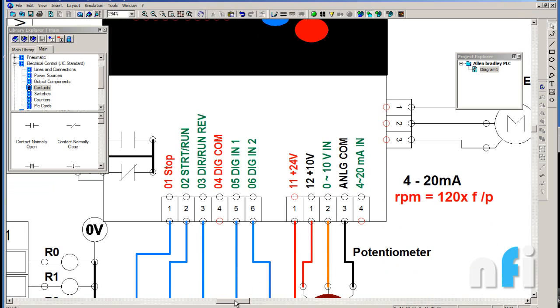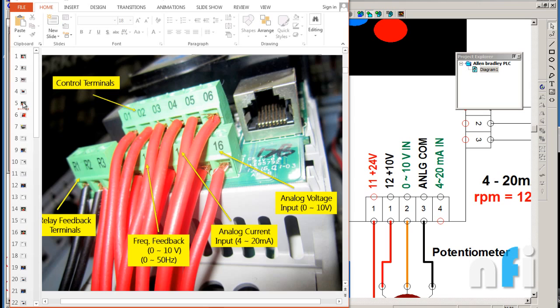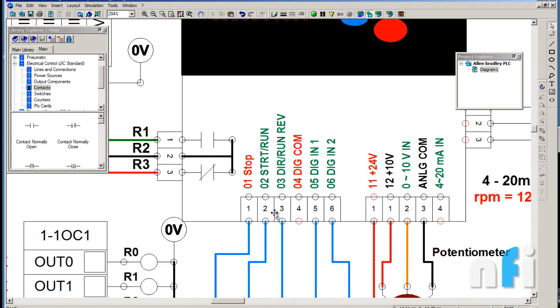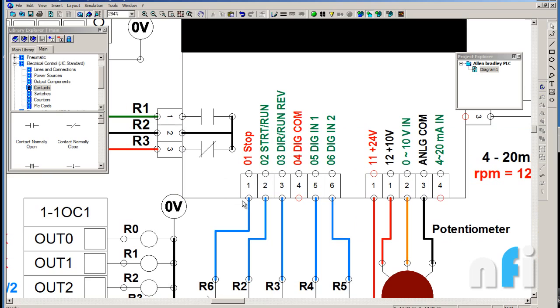These are the control terminals: 1 through 6, and 11 through 24. There are numberings on the bottom of the drive and you can also see them here. Terminal 01 is stop, 02 is start and run, 03 is direction run/reverse, 04 is digital common, 05 is digital input 1, and 06 is digital input 2. These are external terminal inputs — similar to M0 to M5 on a Delta VFD. This version has two digital inputs, though some versions may have more.